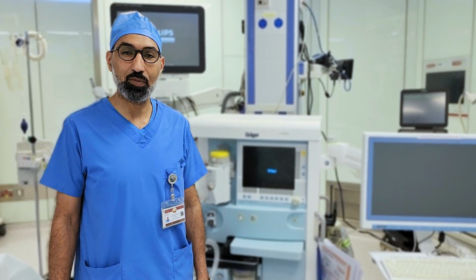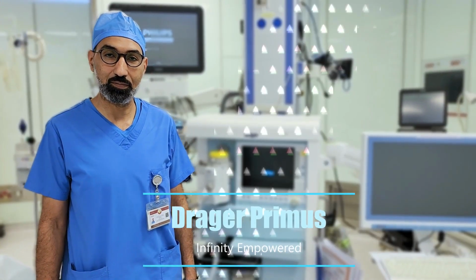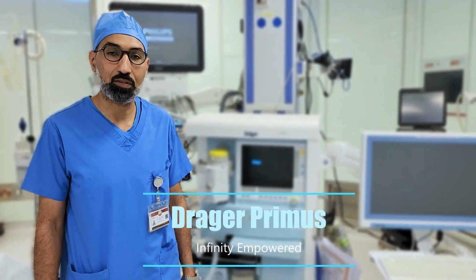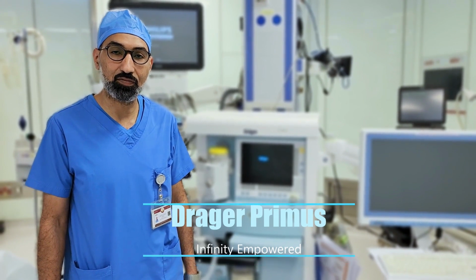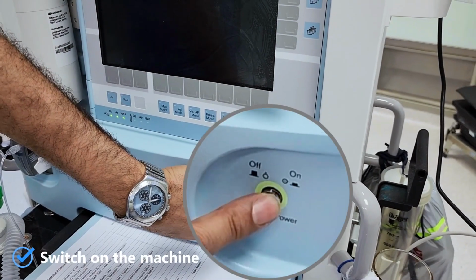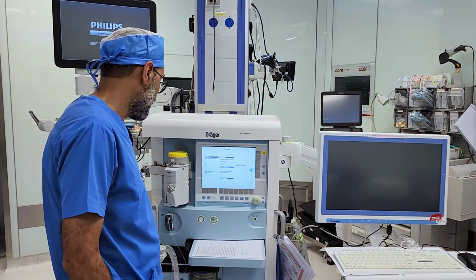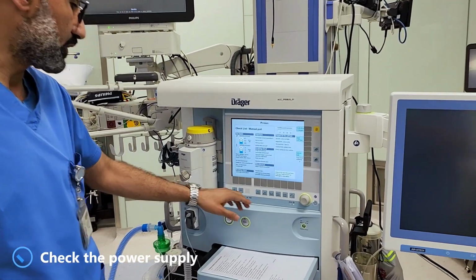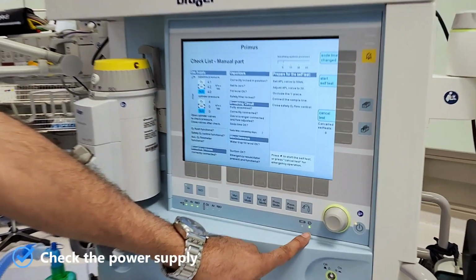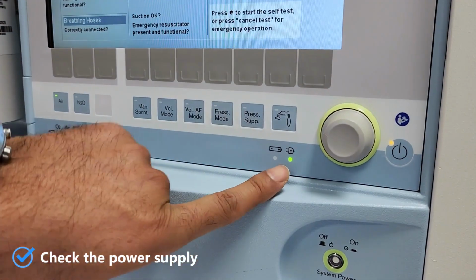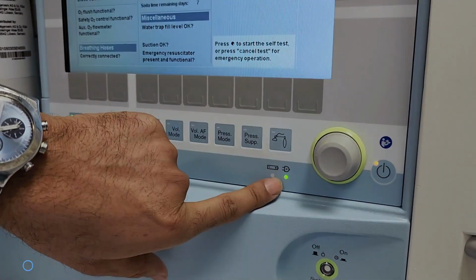Today I am going to talk about the Anesthesia Machine Drager Primus, about calibration and some safety features of the machine. To switch on the machine, you have to press the on-off button. First thing to do is make sure that the machine is connected to the power supply. For that, check whether this LED indicator for power shows green.